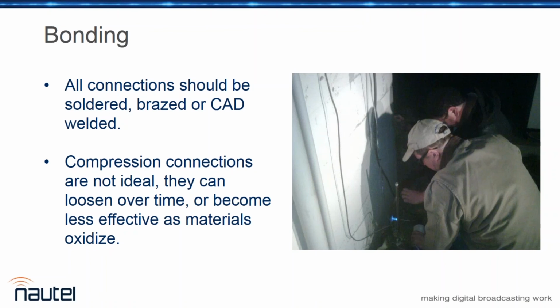That's true enough. So brazing is certainly an option, and that's what we're looking at here. This is a station owner and his contract engineer, and the owner's the one doing the brazing. You'll notice from the flash that it's not being done during the daytime. They had a compression connection, a 2-gauge ground wire coming out of the building through one of those screw-down compression connections onto the ground rod.